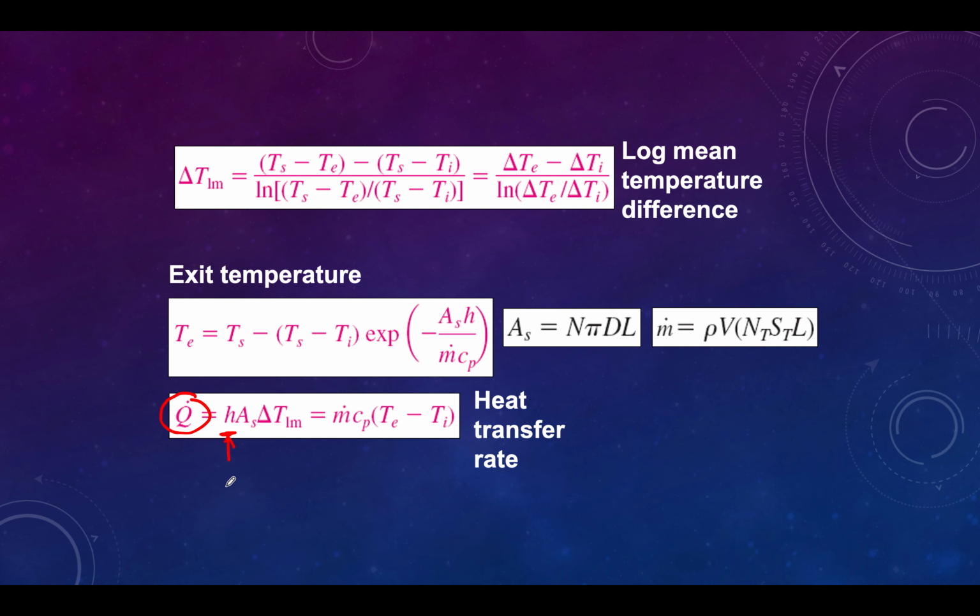You determine V maximum, substitute into the Reynolds number, and from the Reynolds number you see table 7.2 to find the Nusselt number equation, and then substitute to find the Nusselt number. If your number of rows is below 16, you have another table to refer to, and then find the Nusselt number and equate it with Nusselt number equal to HD over K to find the heat transfer coefficient.